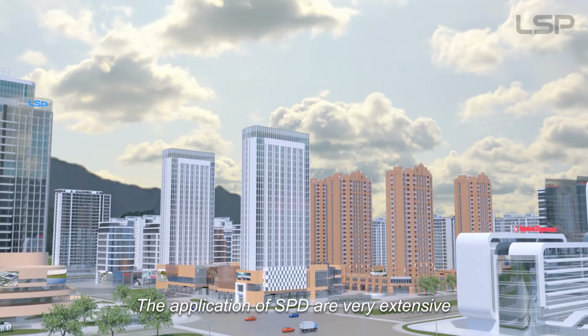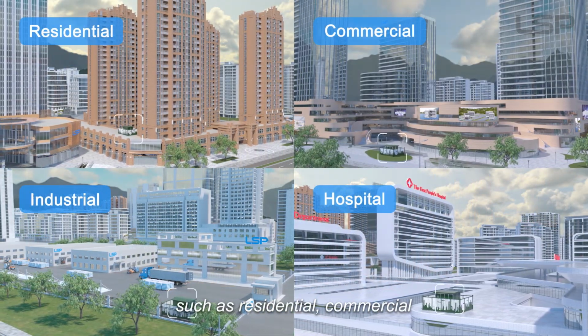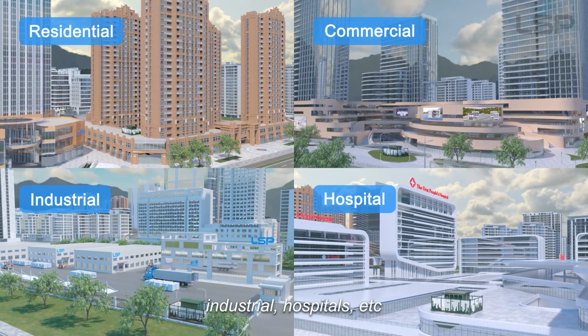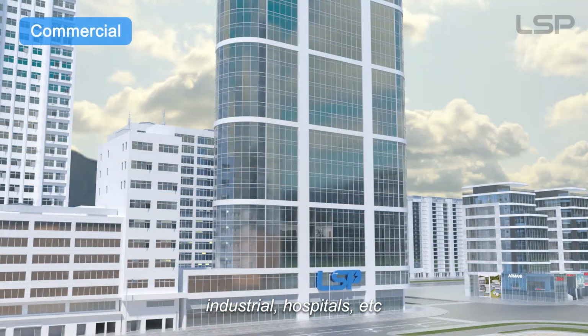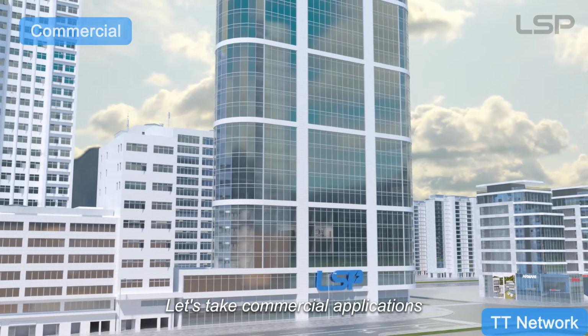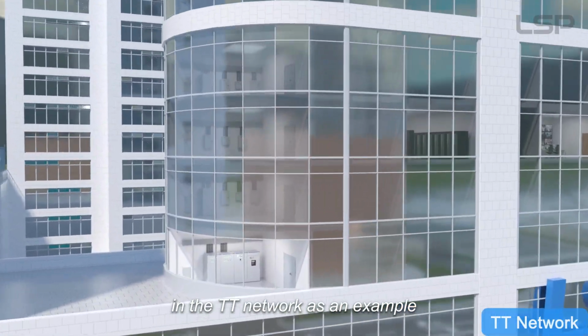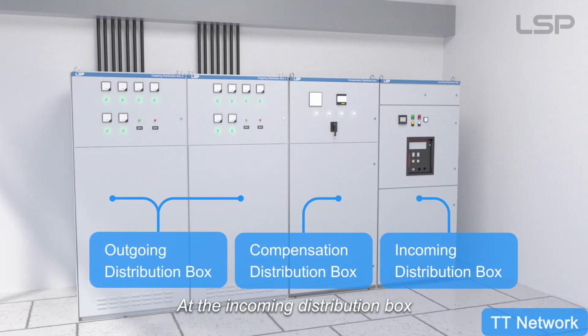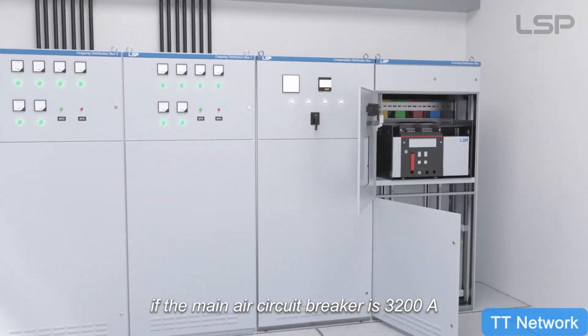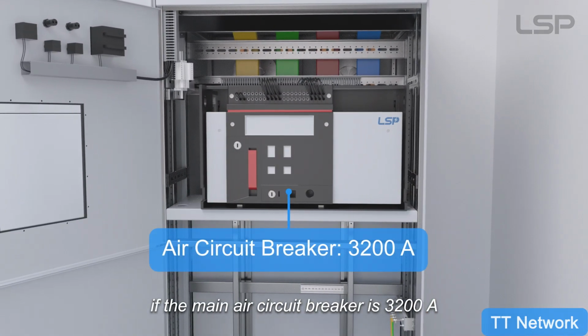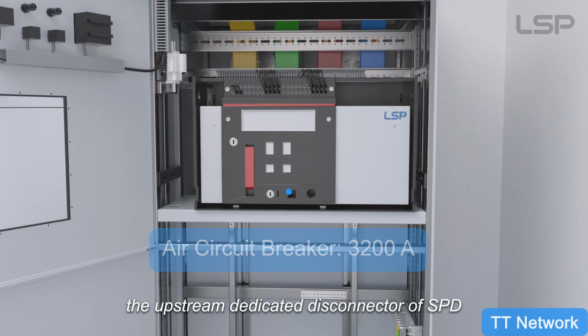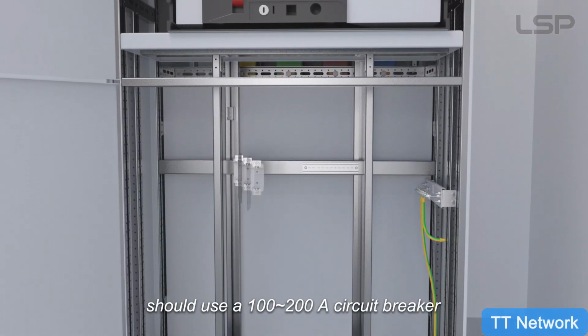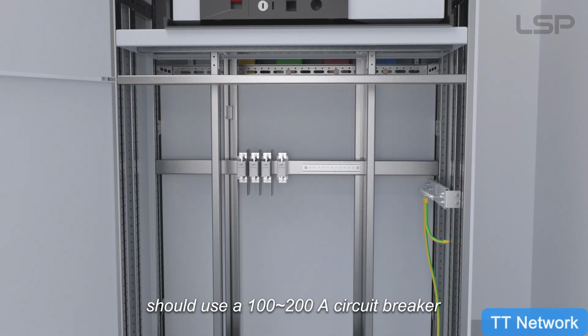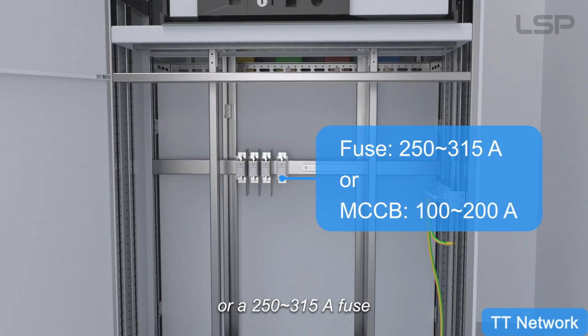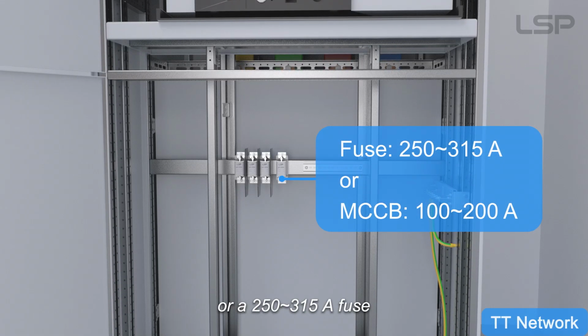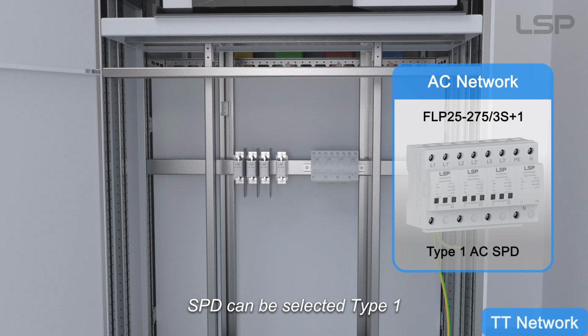The applications of SPD are very extensive, such as residential, commercial, industrial, hospitals, etc. Let's take commercial applications in the TT network as an example. At the incoming distribution box, if the main air circuit breaker is 3,200 amperes, the upstream dedicated disconnector of SPD should use a 100 to 200 ampere circuit breaker or a 250 to 315 ampere fuse. SPD can be selected type 1.